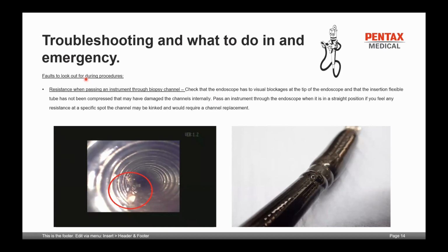Another way to check is to lay the endoscope in a straight position and then pass an instrument through. If you feel any resistance at a specific spot of the channel, 9 times out of 10 there's a kink in the channel or damage to the instrument, as you can see in this image over here. This image on the right, maybe your left, is a damaged insertion tube, which has obviously impacted the instrument channel as well.